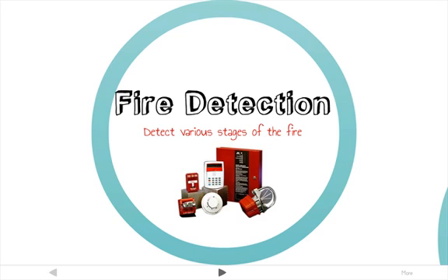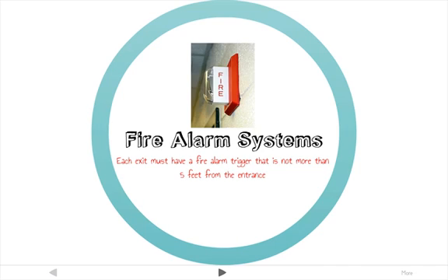The main goal of the fire alarm and detection system is first to protect lives and second to protect property. There are four stages of fire progression: the incipient stage, the smoldering stage, flame, and then heat. Fire detection equipment serves to detect all of these stages. Depending on the type of system, it may detect fire before smoke has even started — it could be alerted by heat. A smoke detector in your living room or bedroom is set to detect smoke. Codes require that fire alarm systems be both audio and visual. In large buildings where firefighters may not be able to access the higher floors for some time, the alarm must be a voice alarm that issues specific safety instructions. Each required exit must also have a fire alarm that's not more than five feet from the entrance, to help occupants locate the exit during an emergency.